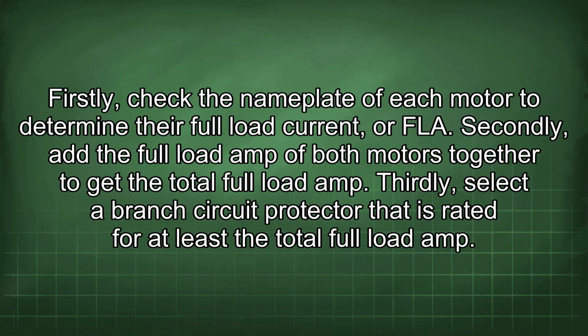Firstly, check the nameplate of each motor to determine their full load current, or FLA. Secondly, add the full load amps of both motors together to get the total full load amps. Thirdly, select a branch circuit protector that is rated for at least the total full load amps.